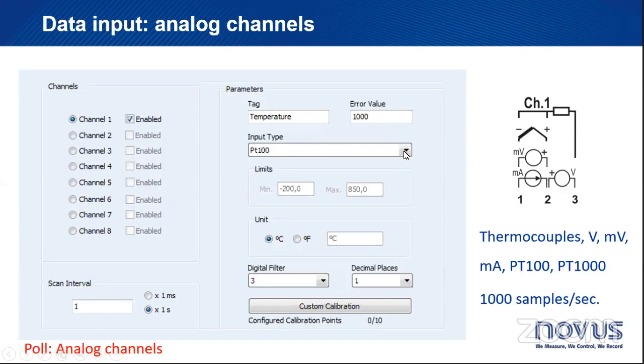Input type is a drop-down list. So you click here, you see all the possible parameters, okay? PT100, thermocouple type K, J, T, R, S, whatever. 4 to 20 milliamps, 0 to 10 volts, 0 to 5 volts. I'll go to the limits on the next example, right? So unit is either degrees Celsius or degrees Fahrenheit, in your case here in the United States. Digital filter. What is digital filter? Well, digital filter is a sort of filter that will slow down the answer. It will slow down the answer of the input.